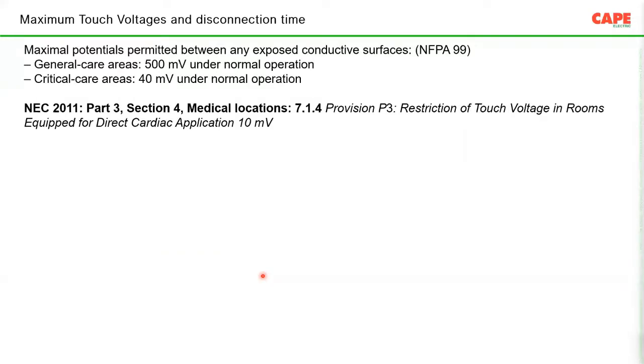Now, in order to reduce the accidents or the amount of the problem, different standards recommend different requirements. For example, the NFPA 99, which is followed in America, says in general areas under normal condition, more than 500 millivolt shall not be allowed, and in critical areas, more than 40 millivolt in normal condition shall not be allowed. That means all the exposed and extraneous conductive parts must be interconnected in such a way that more than this voltage is not experienced between two metallic parts.